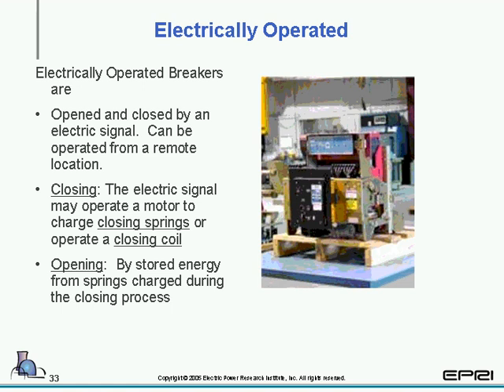Electrically operated, again, as we just spoke about, is that the breaker can open and close by electrical signal and can be done remotely as well as locally. For closing, an electrical signal may operate a motor to charge the closing springs or operate a closing coil. Both of these are considered electrically operated. And then the opening is by stored energy from the springs charged during the closing process.